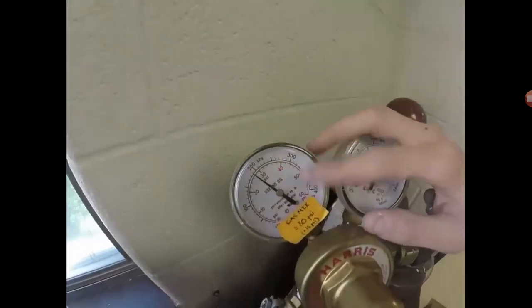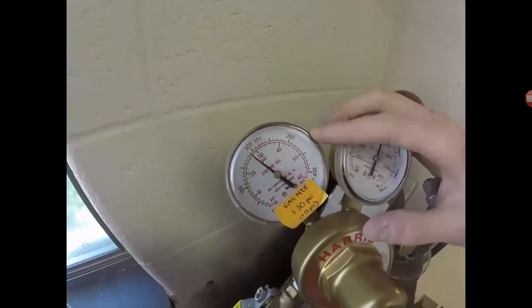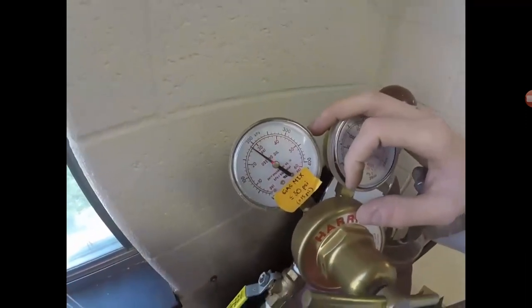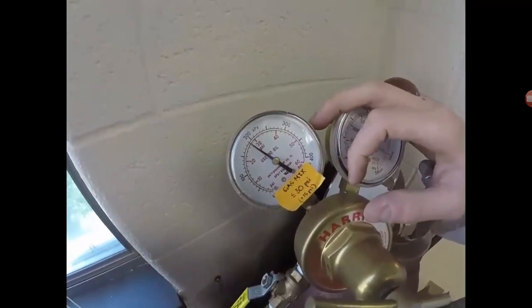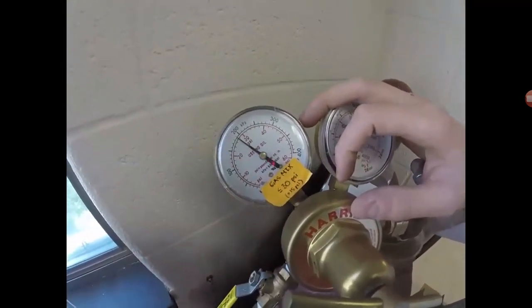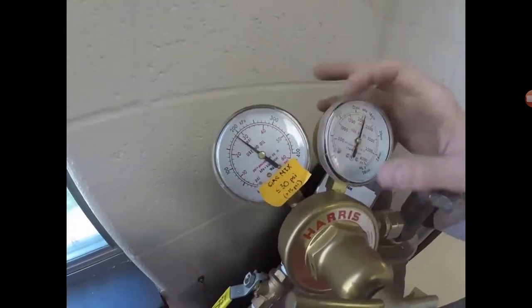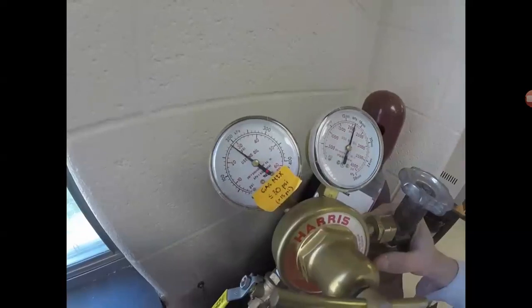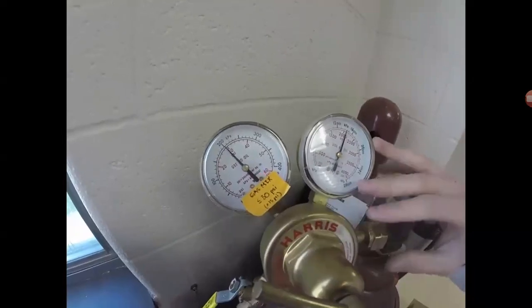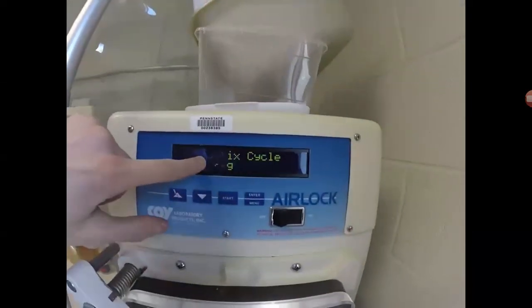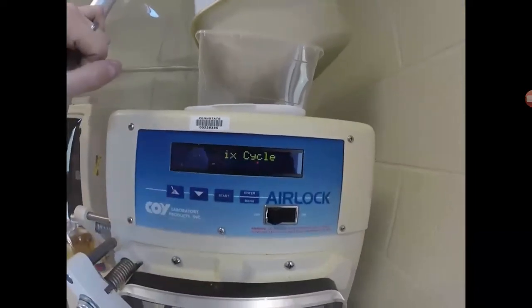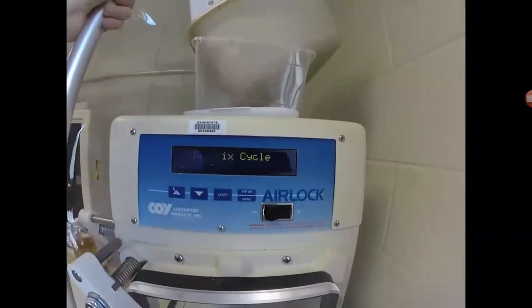So then you can come over here. Because we just changed this cylinder, pressure is a little bit different than where it started. We'll see what happens when it actually starts to flow. Turn this up. Okay, so that's now going to fill the chamber, which you can come back over here. At this point now it says gas mix. So there's gas in there somewhere. And mix here, which helps you to know which one it's actually doing.